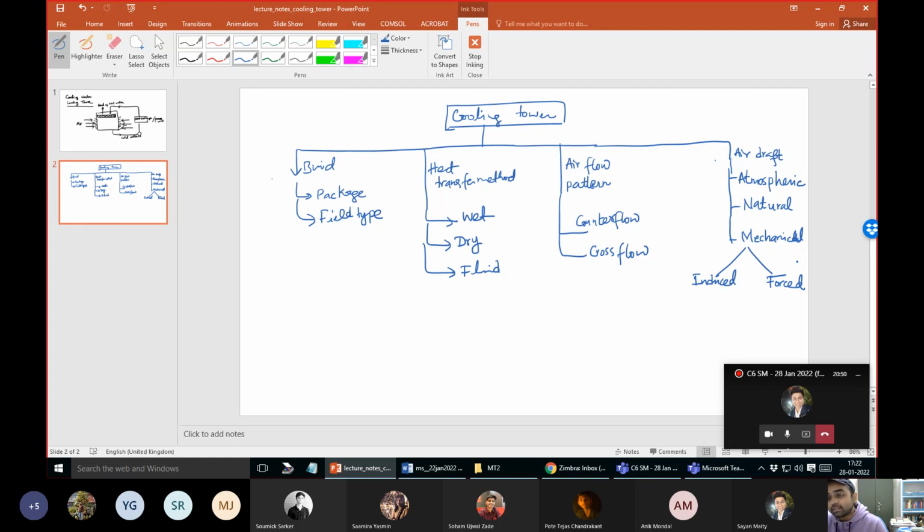But the major difference between these two types and the wet type is that there is no direct contact of the cooling water on the surface, and because of this, the evaporative losses are significantly reduced. Further, the water is not contaminated by dust and particles that come from the air. Though that's not a major issue, in the long run it affects a lot.